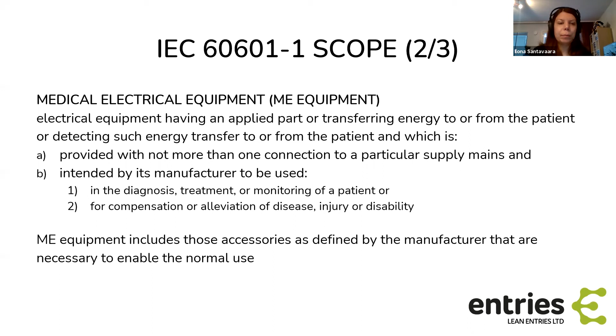So these are basically the medical device definitions in the regulation or directive. And ME equipment also includes accessories that are defined by the manufacturer to be necessary to enable the normal use. So this could be an adapter, for example, or any other thing like tubing, wires, anything like that. So basically, if you have accessories, remember to include those in the design for electrical safety and in the testing.